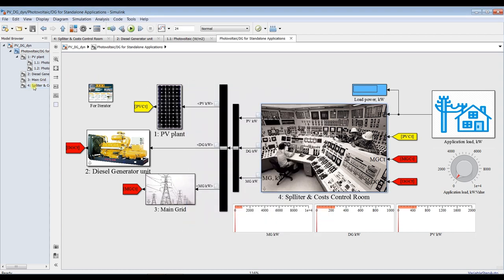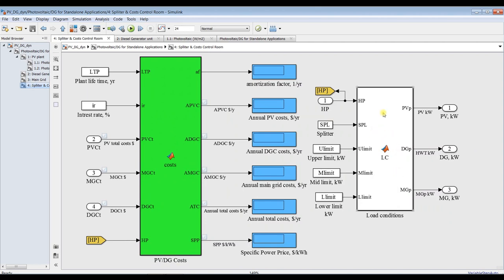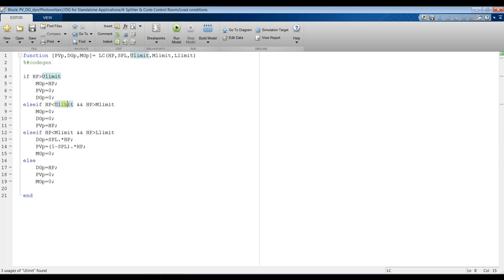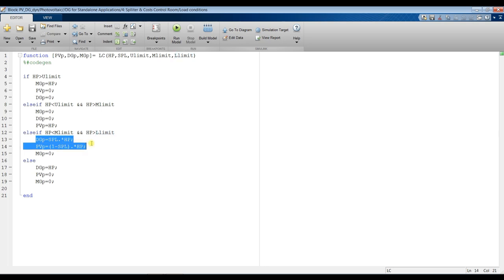Let's go inside here and we can see the load condition. I chose to do the following: if the load power is a little bit higher than the upper limit, I need to utilize the main grid power — no load on photovoltaic and no load on diesel generator. If the power is between the medium limit and the upper limit, I need to operate photovoltaic only. If your load is below the medium limit but above the lower limit, I need to utilize a percentage distribution between photovoltaic and diesel generator.